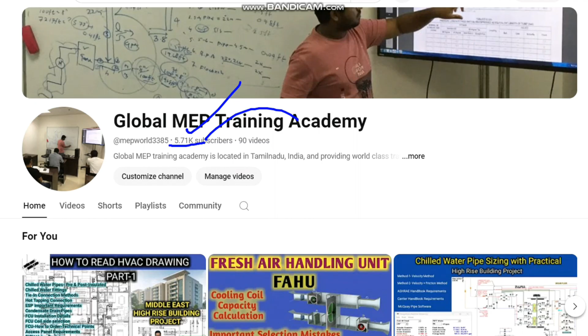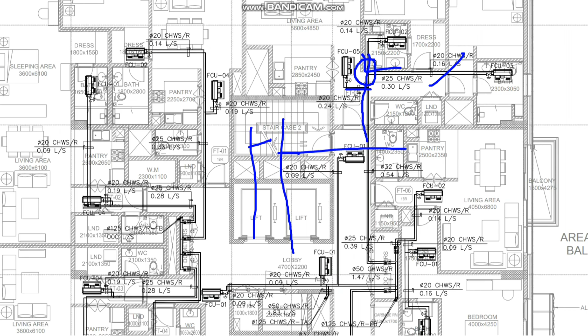Coming to the last point of today's video, the branch takeoff. For example, this is the main line, and from here I have to take a branch for this FCU and this FCU. So how do we take the branch from this main line? If you zoom into this line, we have two connections, supply and return. For the main line, one line I can take straight away like this. For this connection, I can take it straight away. But for this other connection, I have to cross the line, as you can see clearly from the section side.